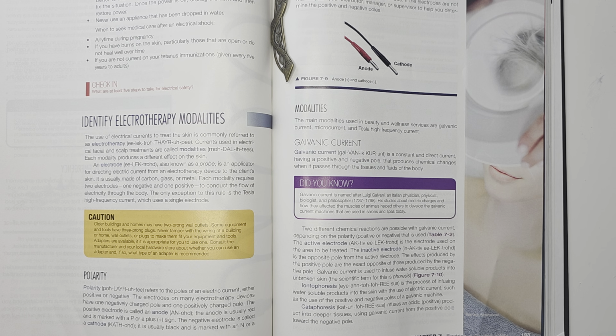Polarity refers to the poles of an electric unit, either positive or negative. The electrodes on many electrotherapy devices have one negatively charged pole and one positively charged pole. The positive electrode is called an anode. The anode is usually red and is marked with a...